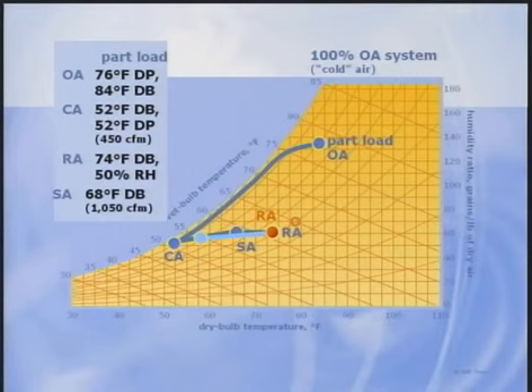The cold outdoor air offsets part of the sensible cooling load in the zone, while the local unit does the rest. Since the central unit delivers air that's drier than that in the zone, it dehumidifies enough to keep the zone at 50% RH. In this case, this approach complies with standard 62.